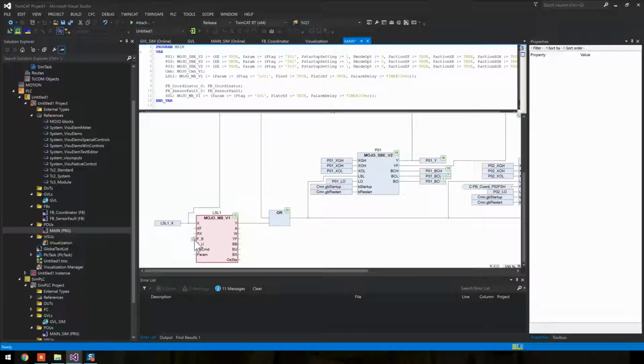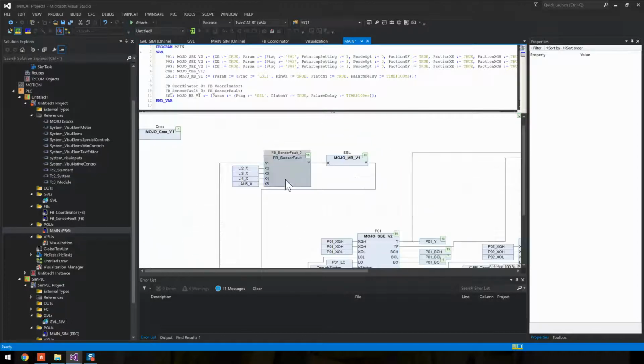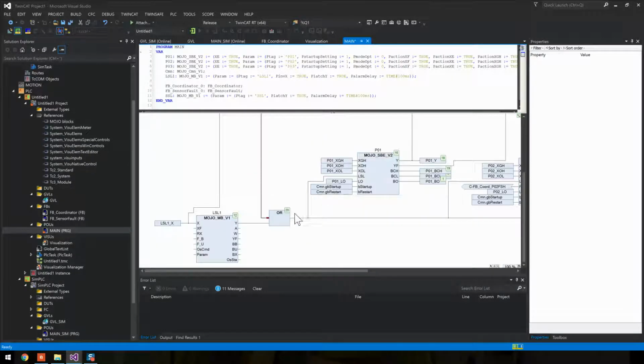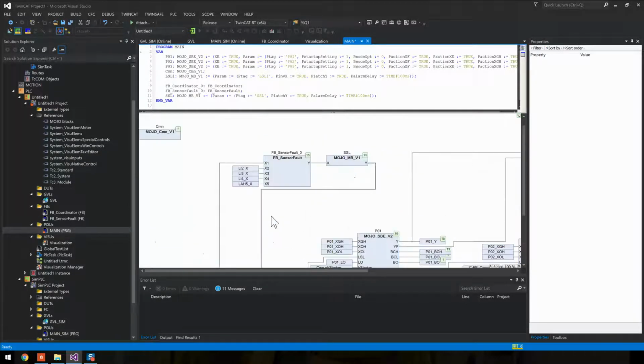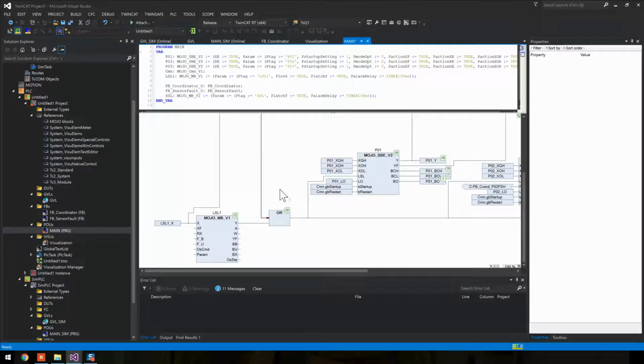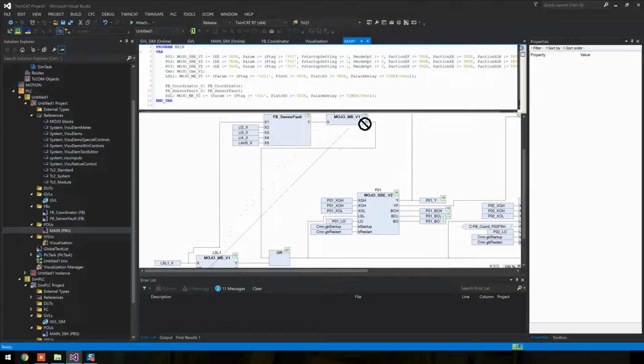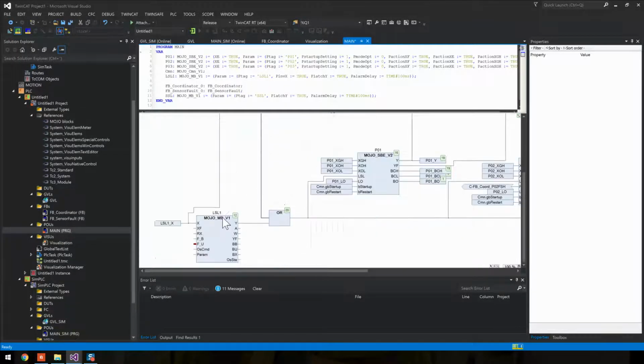So let's use suppression. We don't care about the low level alarm if the low level sensor is faulty. And if we know the low level sensor is faulty, we'll do this exactly same thing. We're gonna stop the pumps, so we're not altering any functionality, we're just altering the display actually. So let's suppress this one if the sensor is faulty.